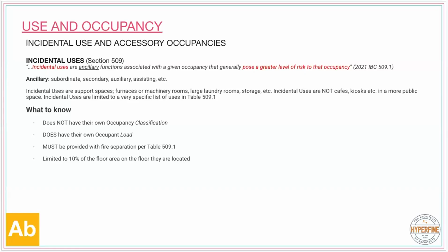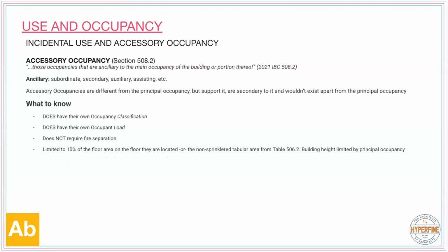So incidental uses, the thing to keep in mind is sort of these 4 bullet points: they're more hazardous than the occupancy which they reside in. They do have to be fire separated, but they don't need their own occupancy classifications. Next, please. All right, so the next one is accessory occupancy.